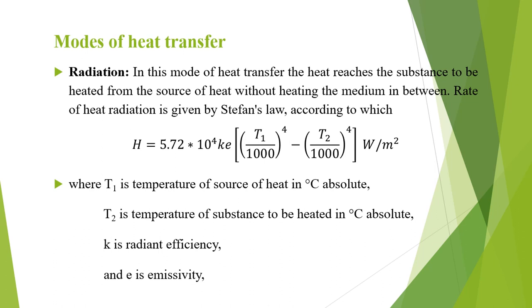The rate of heat radiation is given by Stefan's law: H = 5.72 × 10⁴ × K × e × [(T1/1000)⁴ − (T2/1000)⁴] watts per square meter, where T1 is the temperature of the source of heat in degrees Celsius absolute, T2 is the temperature of the substance to be heated in degrees Celsius absolute, K is the radiant efficiency — its value is 1 for a single element and varies from 0.5 to 0.8 for several elements placed side by side — and E is the emissivity: 1 for a black body and 0.9 for resistance heating elements.